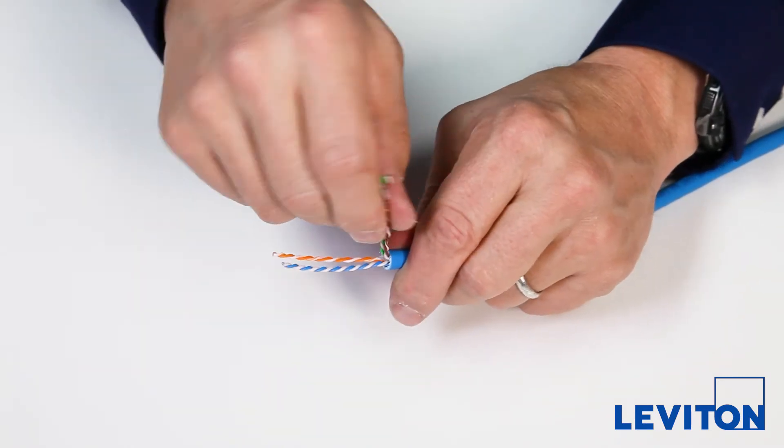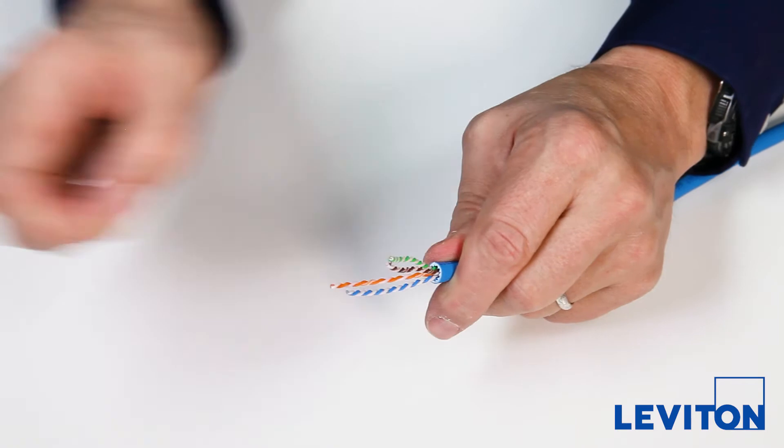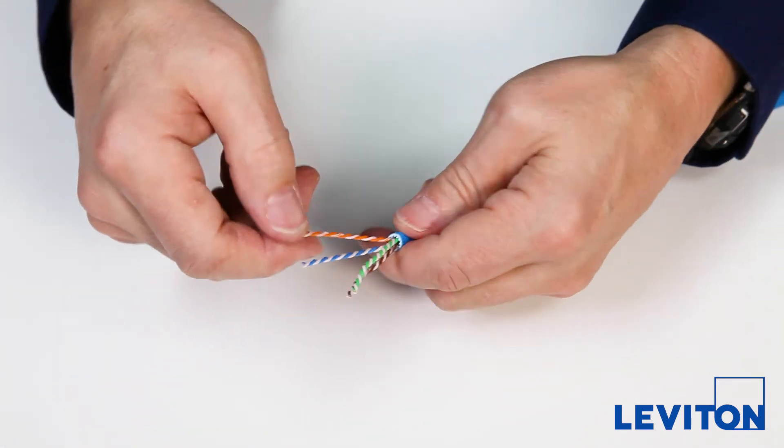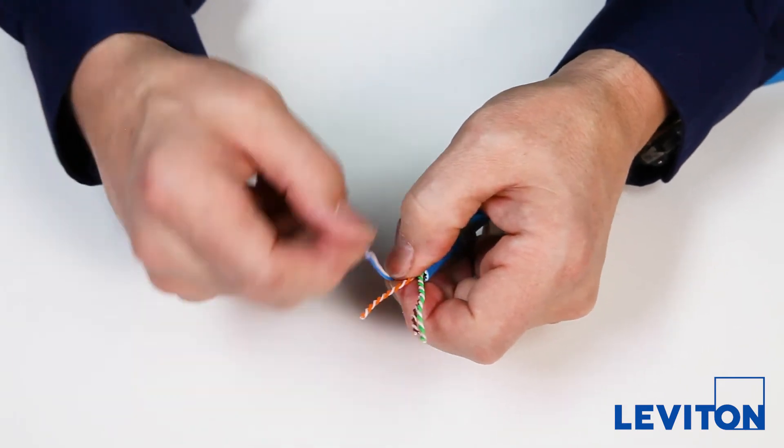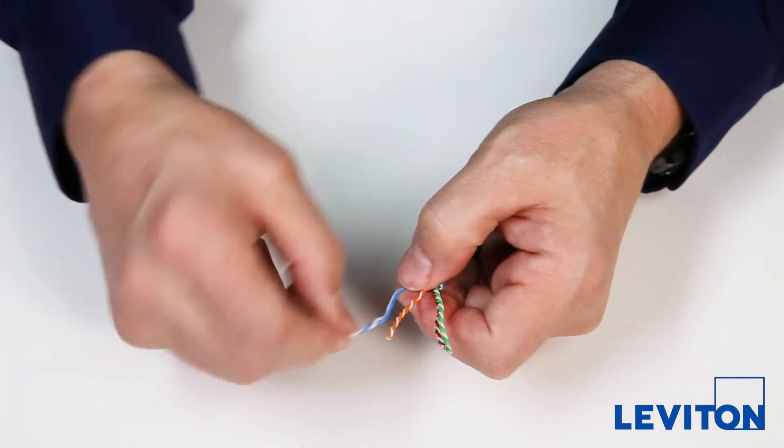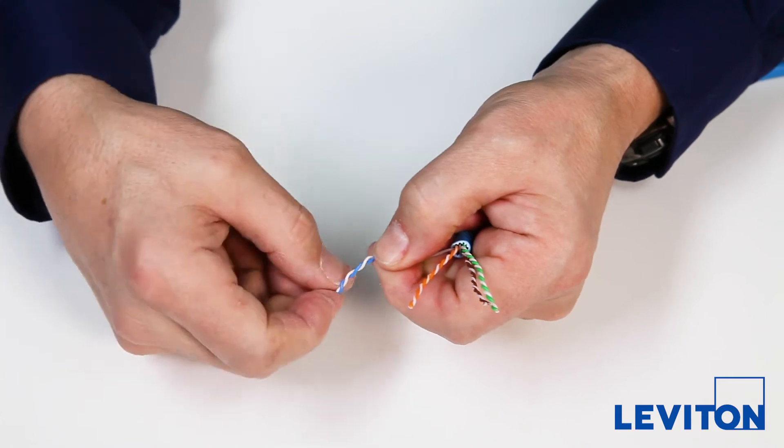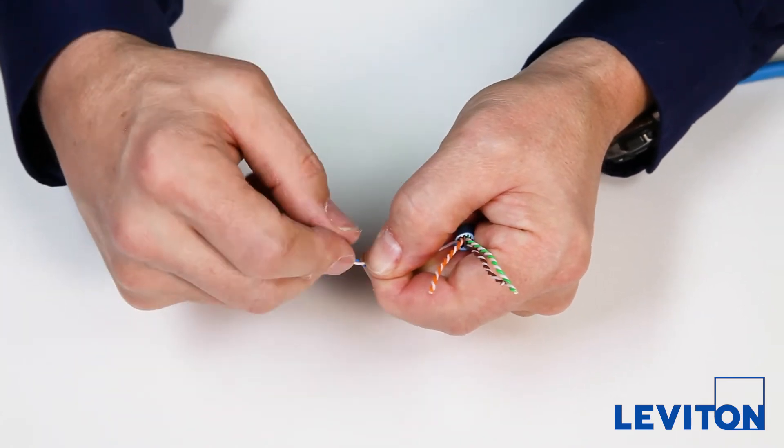Inspect the wire pairs to make sure you didn't damage the insulation or conductor during cable preparation. To straighten out the wires, grasp each pair near its base and untwist it. As you untwist the pair, slide your fingers along both wires to smooth out any kinks.